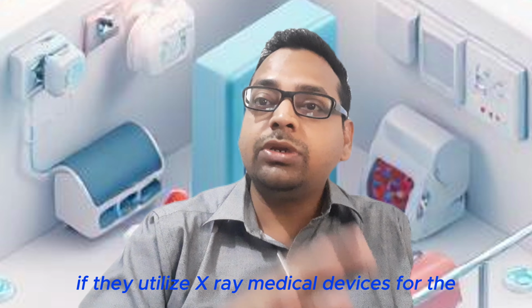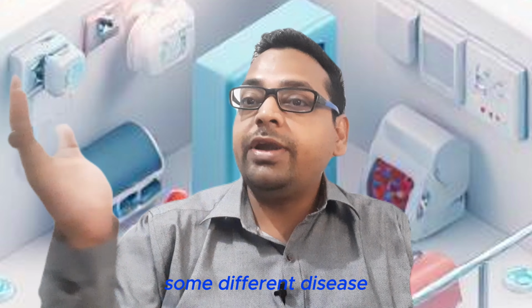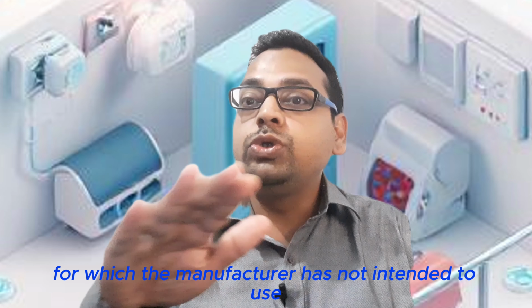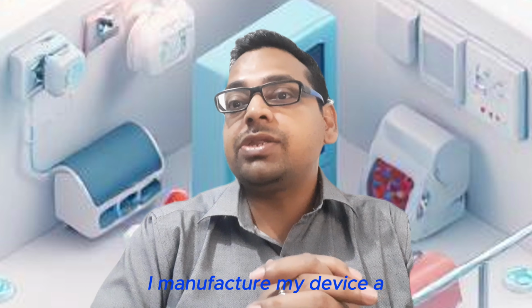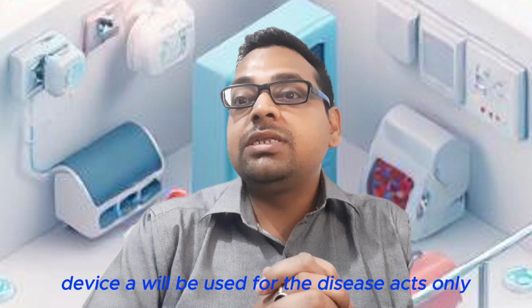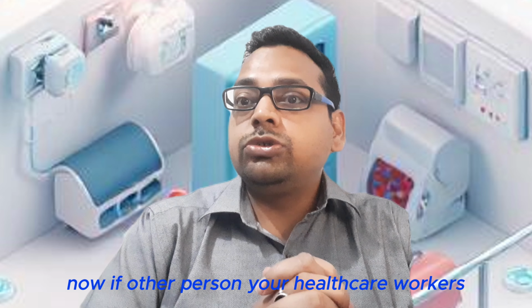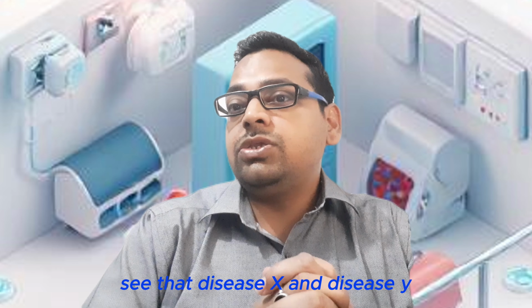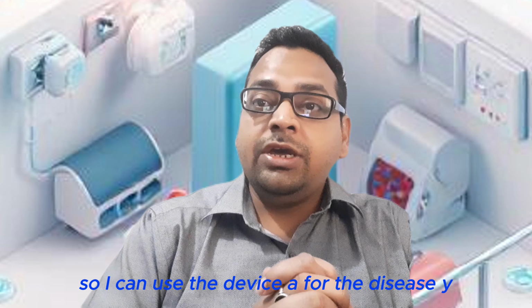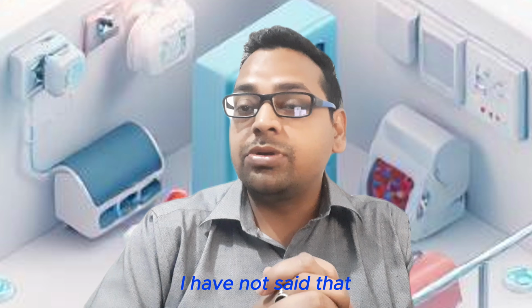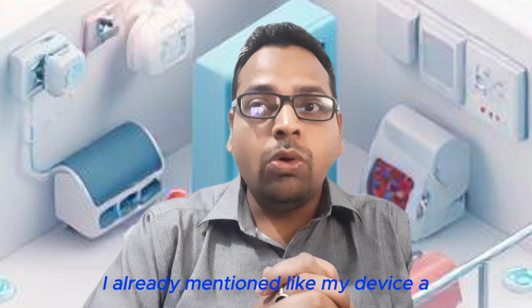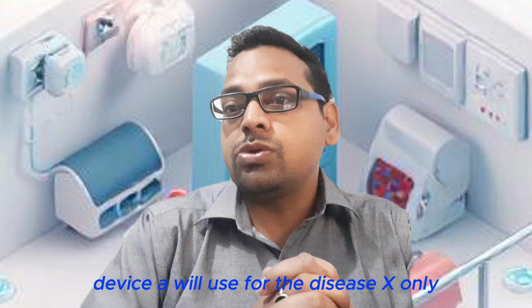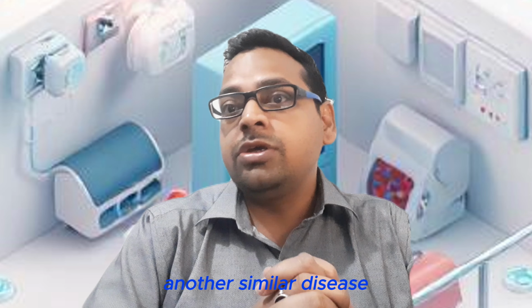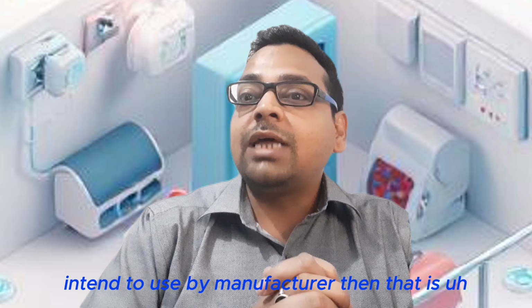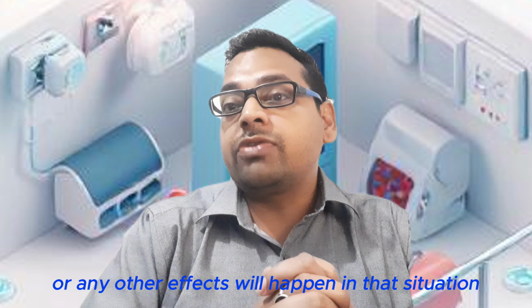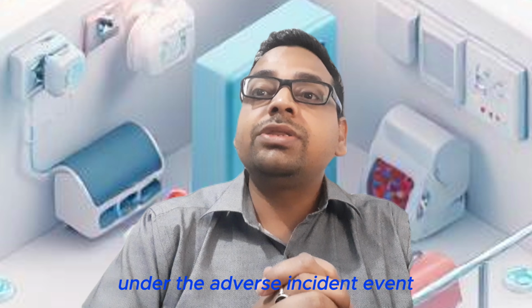But if health workers utilize a medical device for a different disease for which the manufacturer has not intended it to be used. For example, I am a manufacturer, I manufacture my device A and I say device A will be used for disease X only. Now if healthcare workers see that disease X and disease Y are more or less similar, so they use device A for disease Y. But as a manufacturer, I have not said that device A will be used for disease Y. So if a health worker uses it for another similar disease not intended by the manufacturer, and any drastic effect happens in that situation, it will not be covered under the adverse incident event for medical devices.